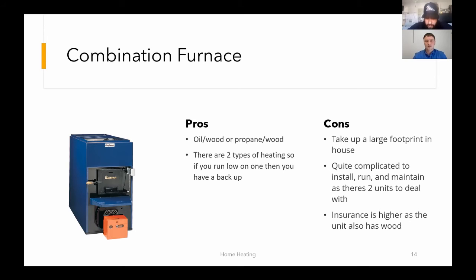These units are quite complicated to install. There are usually two separate units ducted together, so basically you have twice the maintenance and twice the cost to keep them going. Two thermostats upstairs, lots of wiring and relays to go with that. They are complicated units, but if they're done right and the customer is shown proper use and handling, they are good units as you have a backup. So I like to use those units as well.